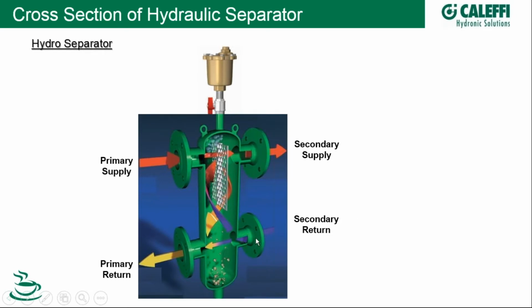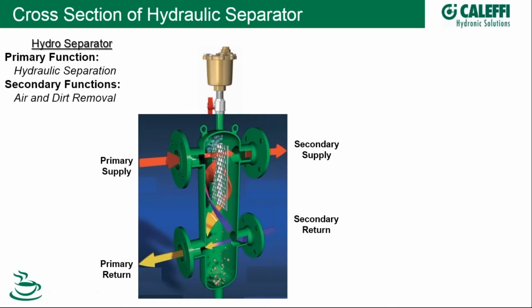Typically, debris in a hydronic system has a specific gravity higher than water, meaning it will sink in water. And because you are slowing down the velocity of the fluid as it enters any type of chamber like this, you get some separation, but not dedicated for dirt elimination. So the primary function of a device like this is hydraulic separation. But secondarily, you do get the added benefit of some air separation, in some cases adequate enough to have no other air separators on your system, and some dirt removal simply by trapping it down here.